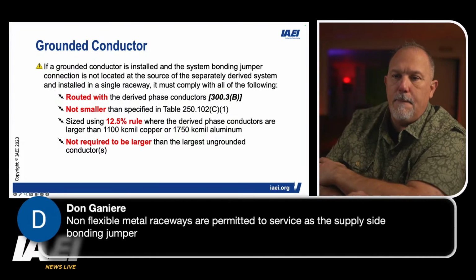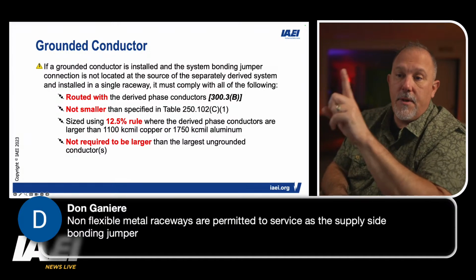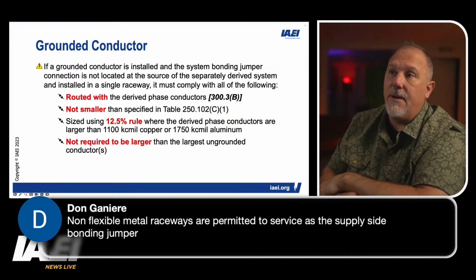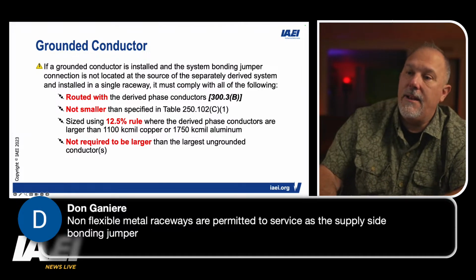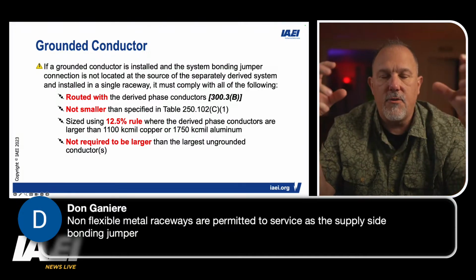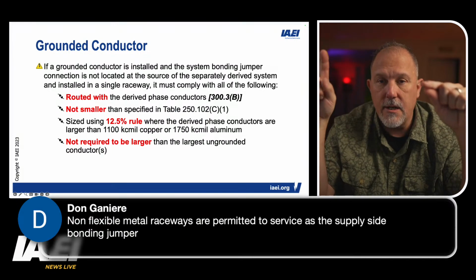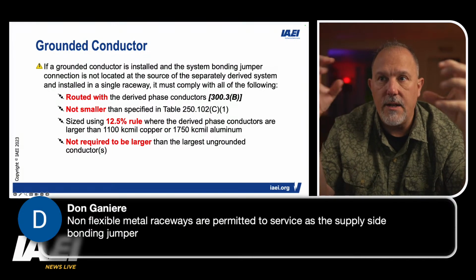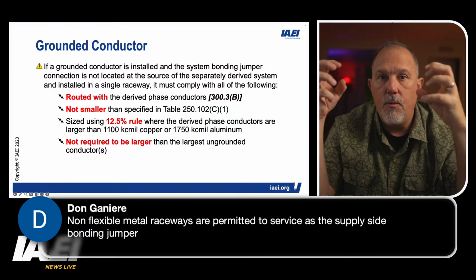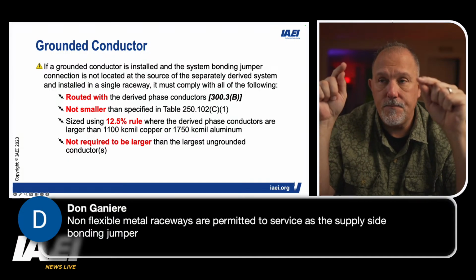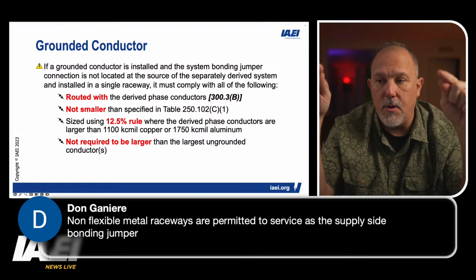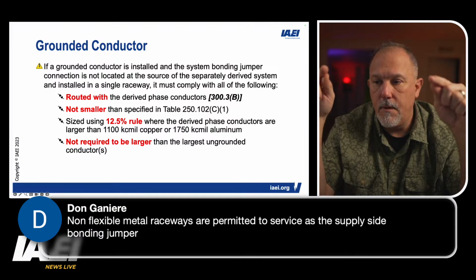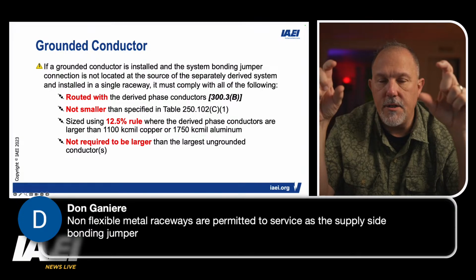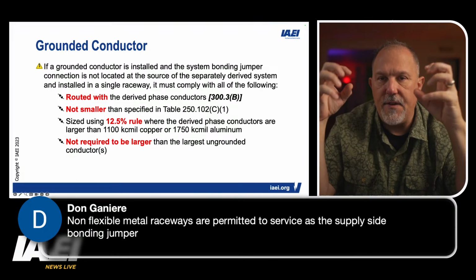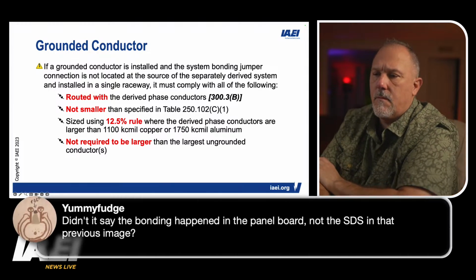Dawn says, non-flexible metal raceways are permitted to serve as the supply side bonding jumper. Yes, I would agree. But you have to have the right fittings. And when I looked at that picture, I wasn't sure if they had the right fittings. So they could pull the conductor through, but you have to have the right fittings on either end for the proper bonding with the structure. And then in some cases, you might have to bond it at the fitting. Hope I got that right.